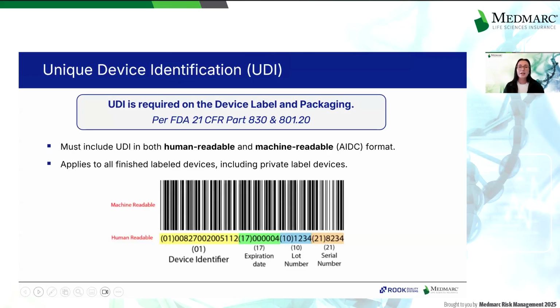So let's talk about unique device identification, or UDI. UDI is required on device labeling and packaging per FDA 21 CFR Part 830 and 801.20. Labeling must include UDI in both human readable and machine readable, or AIDC, format, and applies to all finished labeling devices, including private labels. I have included an example to show and add clarity to the different components of the UDI label for general context.